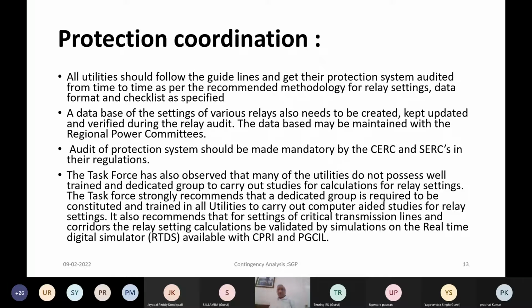But we have really not gone to the level of protection audit where you can verify, line by line, the complete setting program, which runs into hundreds of lines, unlike the earlier version of static relays or conventional relays. So there is a need to do this in an automatic way, where the soft file of the recommended setting is compared automatically with the actually loaded file in the relay. And this is basically the recommendation of the task force, so that actual verification of every parameter of the setting can be done.